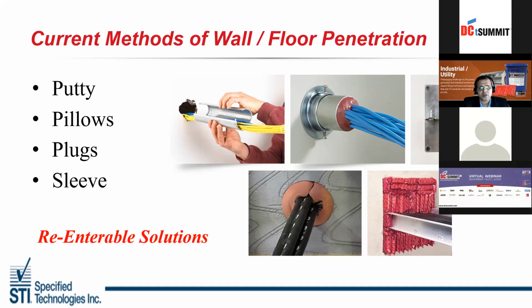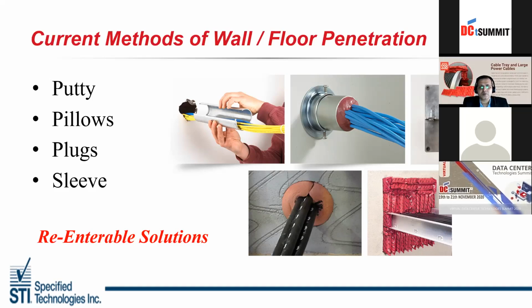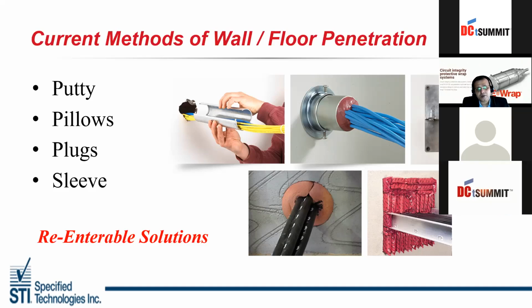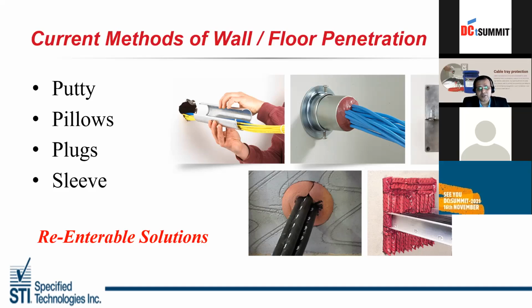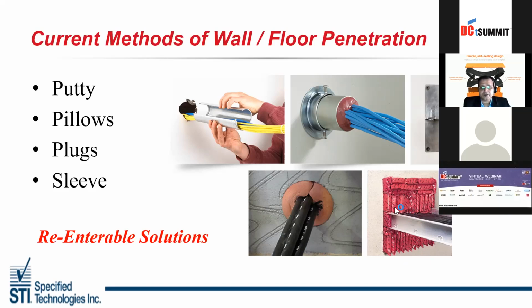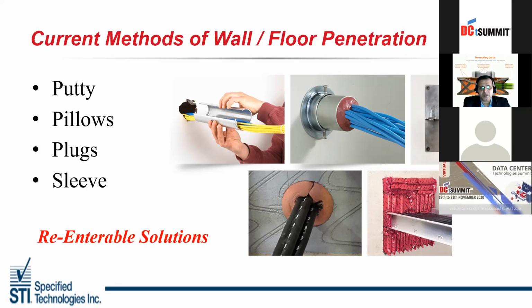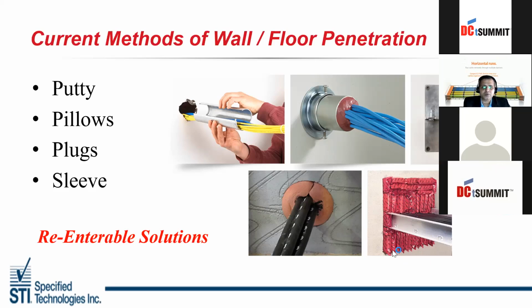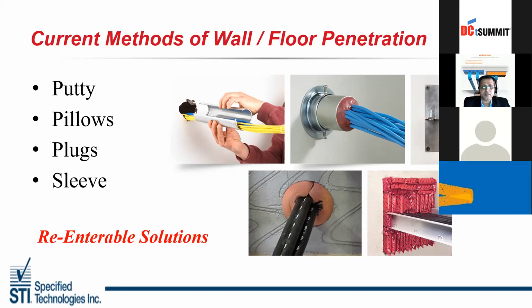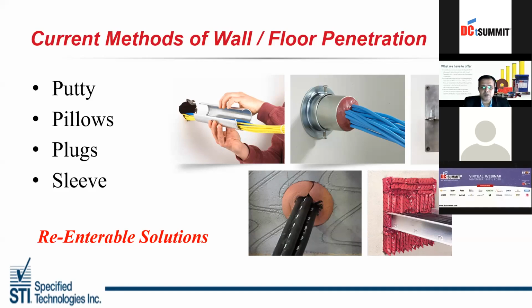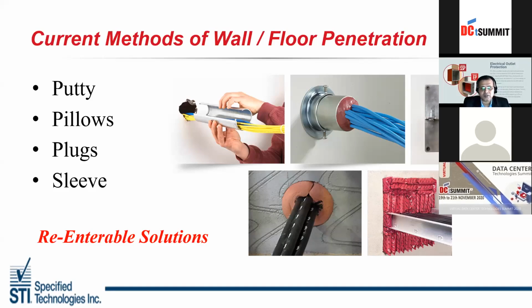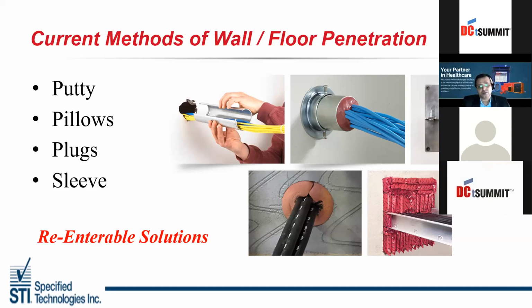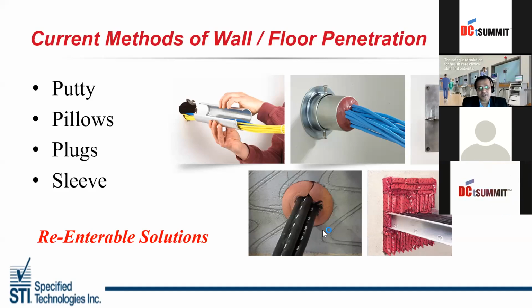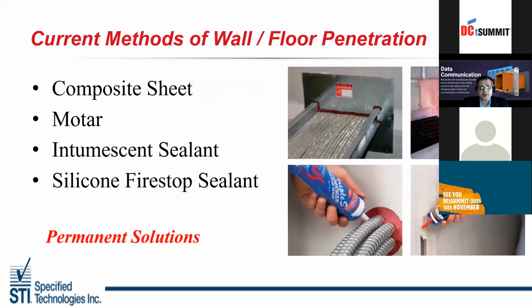These are re-enterable solutions. Putties are like clay, which when the cables are pulled out, the same putty can be reused in the same scenario. It's like clay, so it will remain as it is. Pillows are stackable ones. If you see towards your right-hand side bottom, the cable tray and the pillows have been installed. So pillows are again a re-enterable solution wherein if a cable has to be changed, the cable guy himself can change the cables. He just has to remove a couple of pillows and he can restack them after the work is done. So the fire stopping will remain as it is. There are no changes needed for the fire sealant guy to come and do.